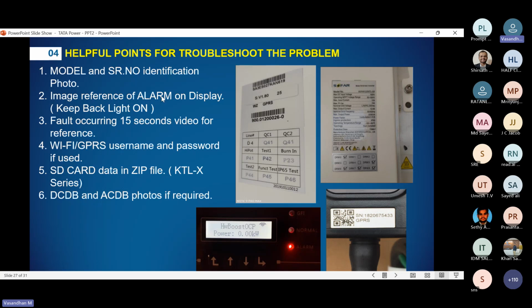For example, a customer has one issue, a software OCP issue. Their first call is, sir, this is the issue we are getting on the display. For example, see here, the display shows hardware boost OCP, which means boost circuit overcurrent protection. OCP means we need to check for an internal fault, any boost circuit or capacitor side issue, anything. These we need to check after checking at our level.